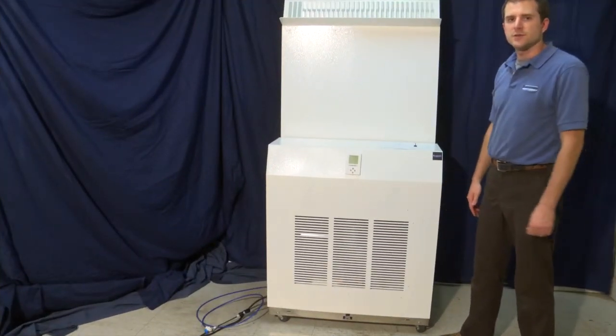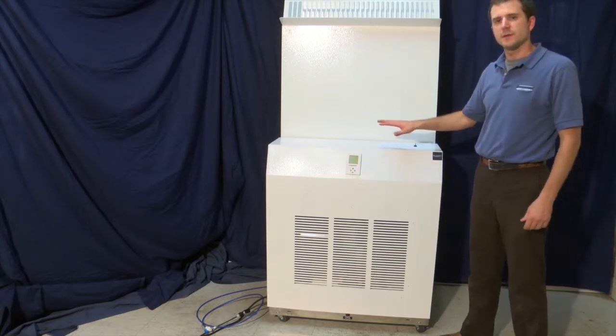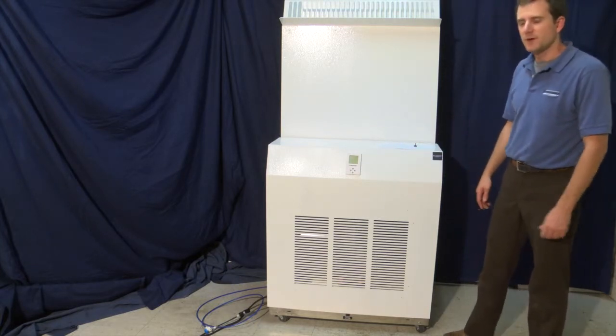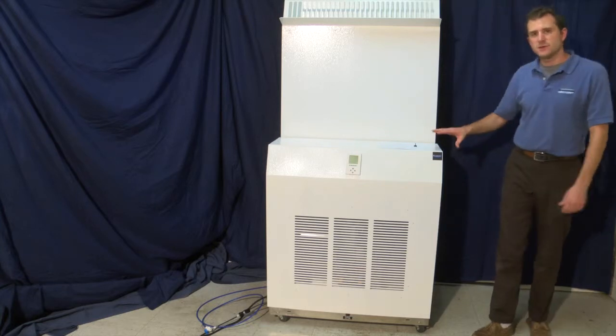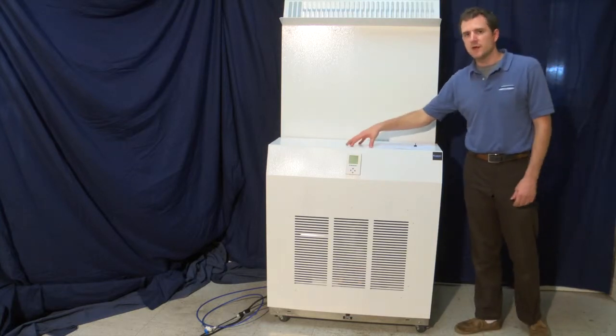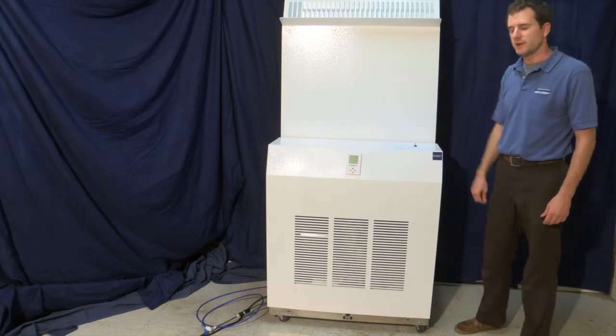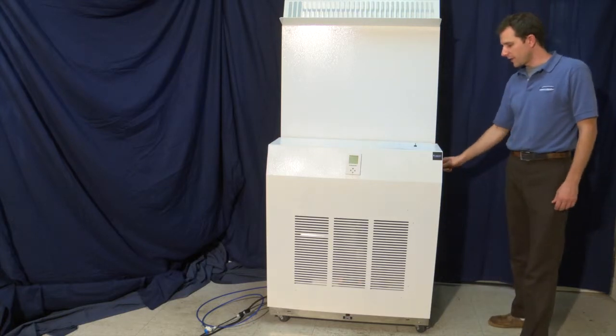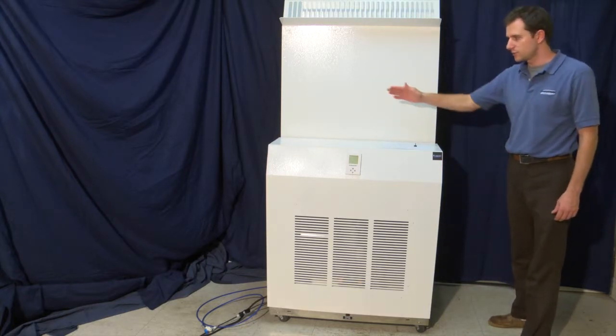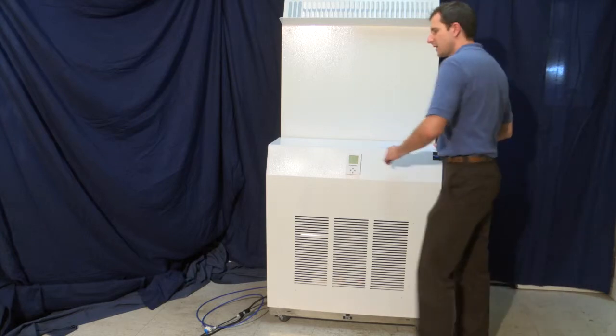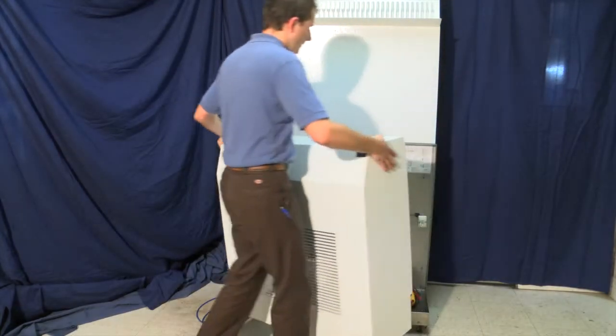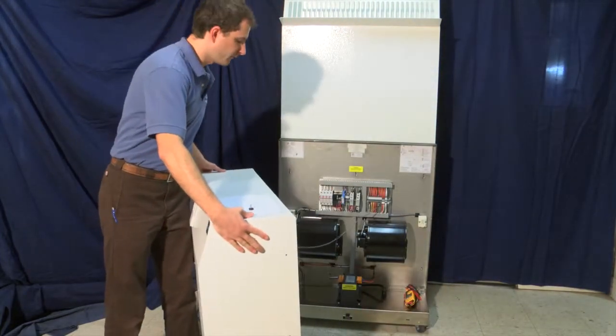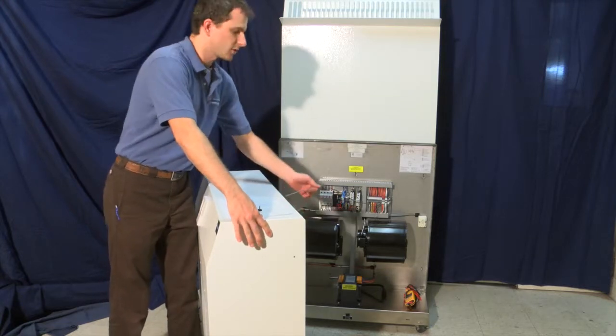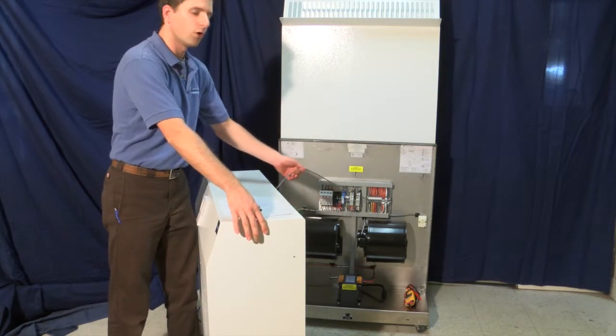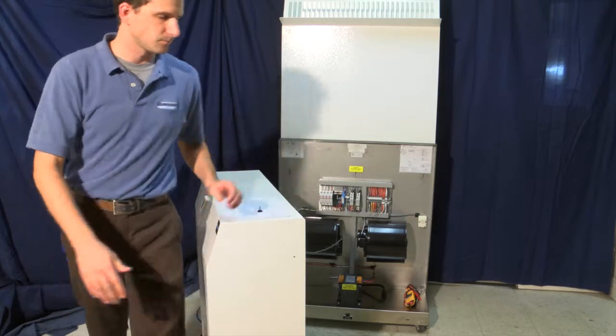We would like to take this opportunity to go over some troubleshooting tips for your Mist-Free Series humidifier. Any troubleshooting done in the Mist-Free Series will require you to remove the fan cover to get at the interface plate beneath. You can remove the fan cover by removing the 6 thumb screws, 3 on each side, and removing the fan cover itself. Note the 3-foot cord between the Humidistat and the terminal block. Be sure not to pull or strain on this cord.